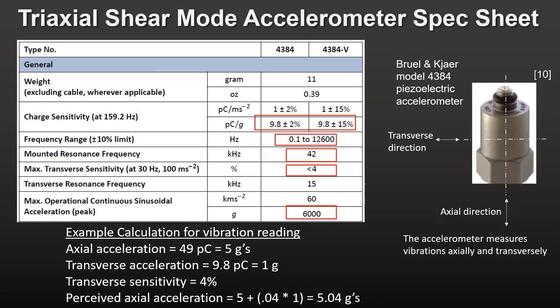The sensitivity of a piezoelectric accelerometer is shown in picocoulombs per g. This is not a great deal of charge, and the only way to measure it is to feed the signal to a charge amplifier and read the voltage output. The sensor can measure acceleration up to 6,000 g, far higher than the capacitive or piezo-resistive types.